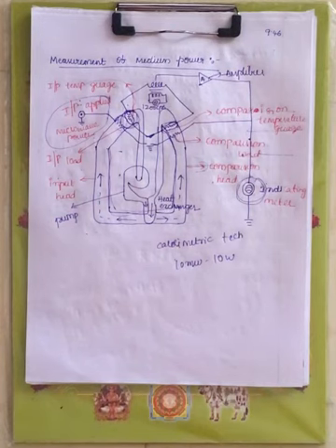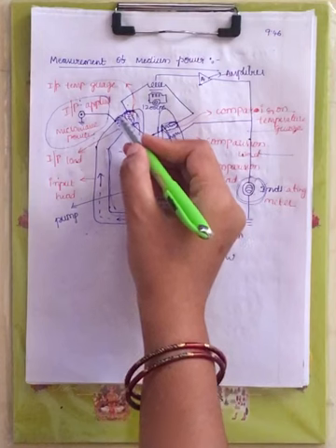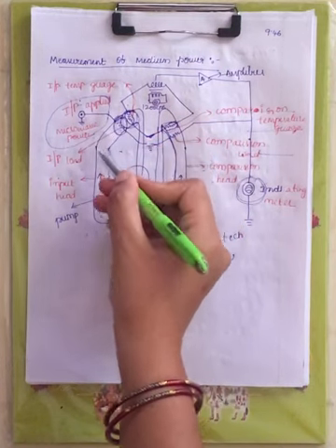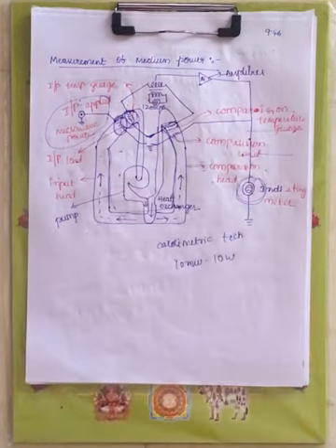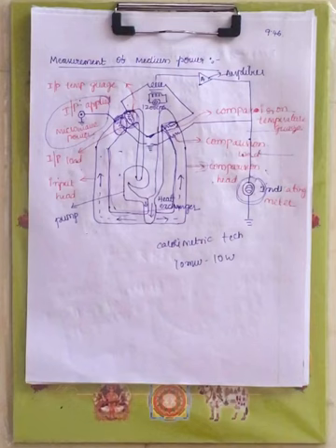Now it works on the principle that the temperature rise of the load is proportional to the microwave power. Here you have the input load and the comparison load. Those loads, nothing but resistances, will vary the temperature, and according to that we measure the microwave power.